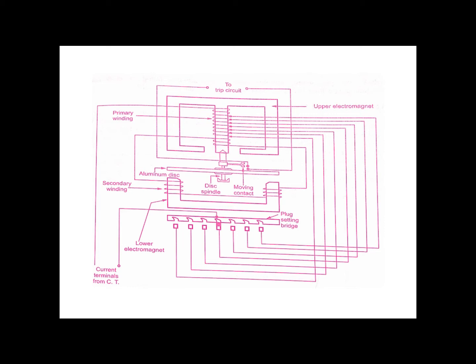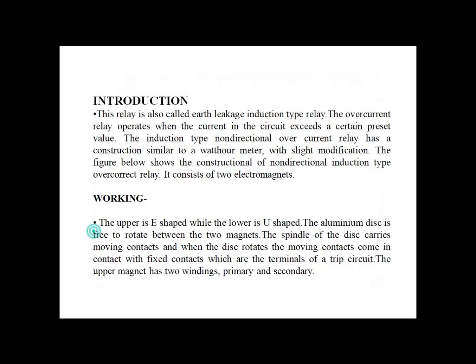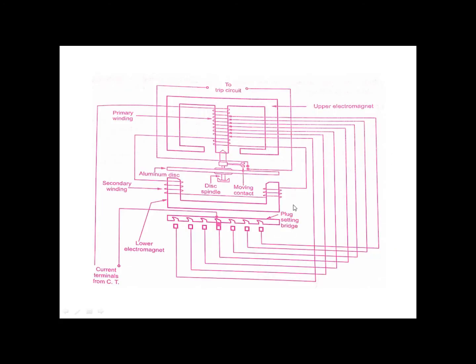The tappings are connected to a plug setting bridge (PSB). With the help of this plug setting bridge, the number of turns of the primary winding can be adjusted, so that the desired current setting for the relay can be obtained.